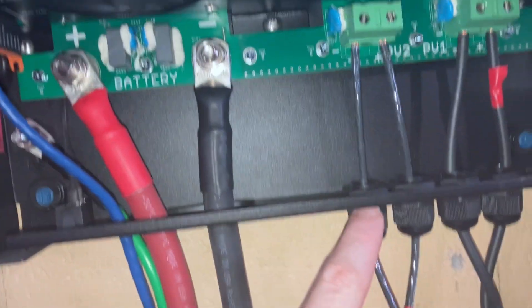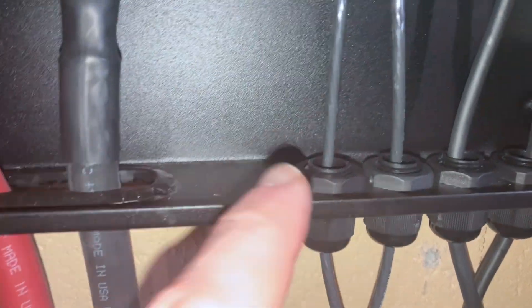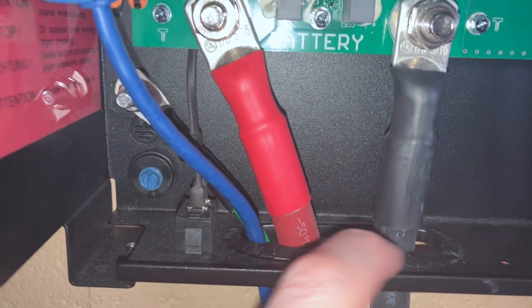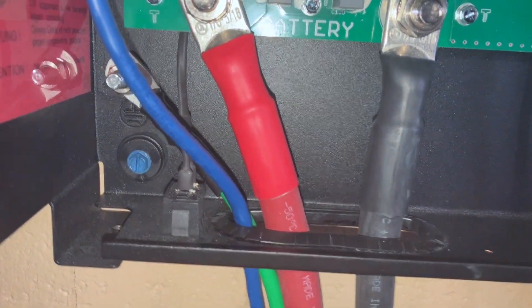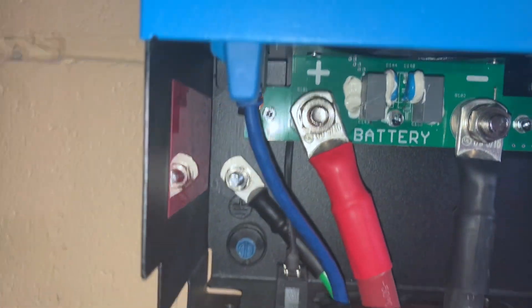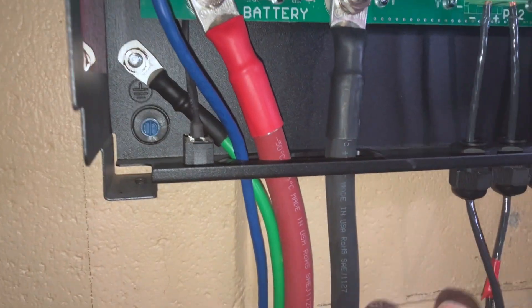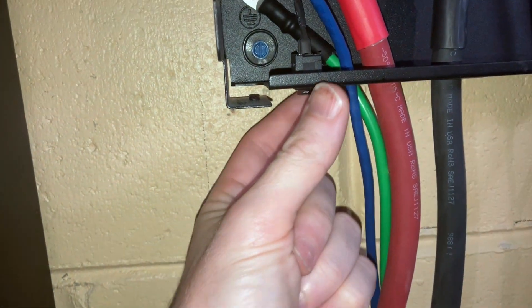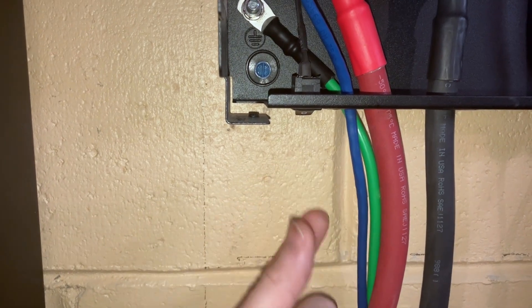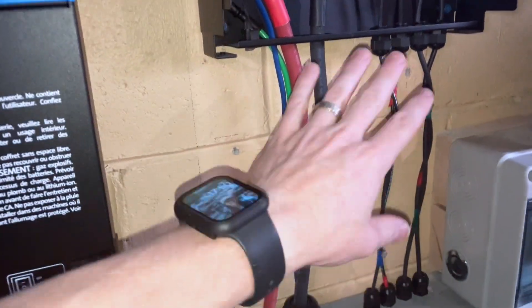Another issue is that, like these inverters, it's not designed for conduit. The cable glands are very close together and do not fit a half inch conduit. You've also got to have this slot here to move your cables around enough to seat them on top of the battery connection. So keep that in mind — if you want the conduit look, you're not going to be able to. I am trying to figure out a way to make a custom plate to come underneath so I could run the conduit up into that plate for a more visually pleasing look.